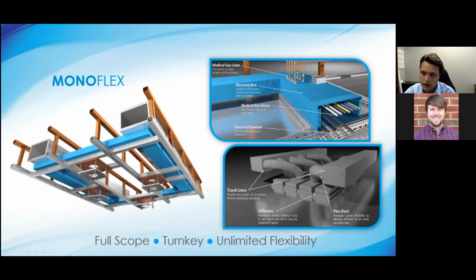This is a structural grid suspended about 11 inches above the ceiling that allows you to mount a boom literally anywhere within the entire array. Right above that is an electrical raceway that brings conduit and med gas to the edge of the array, which then handles distribution to any devices requiring it.